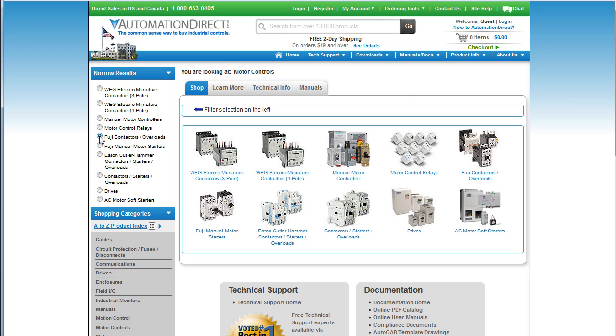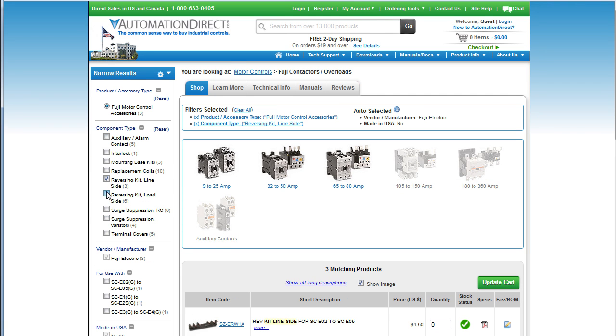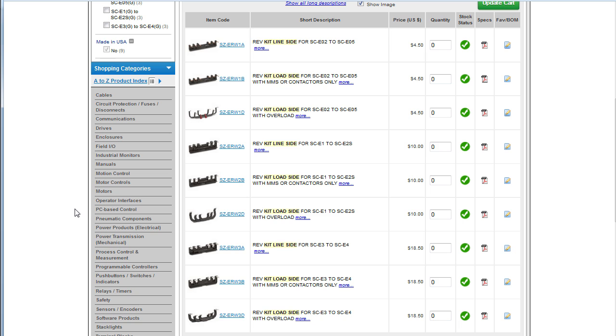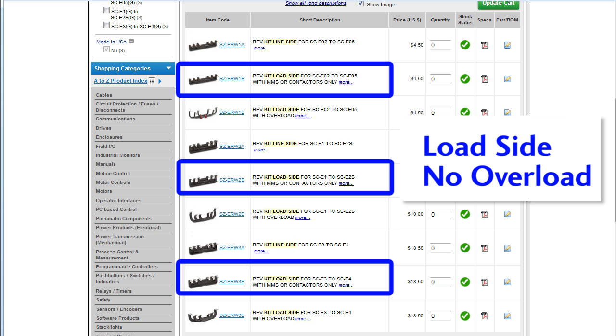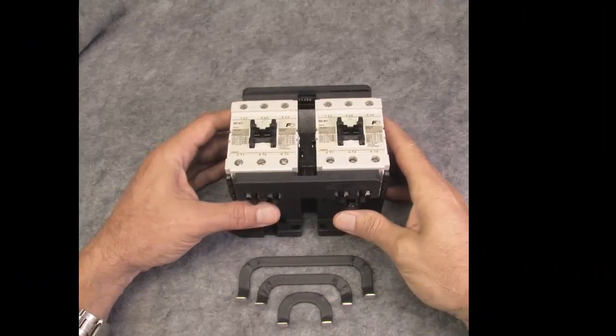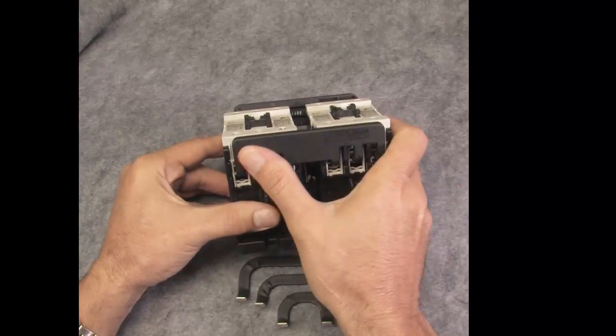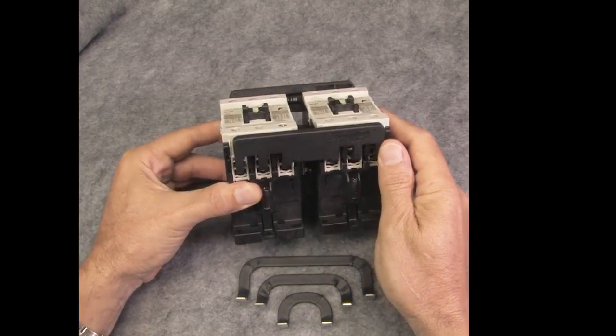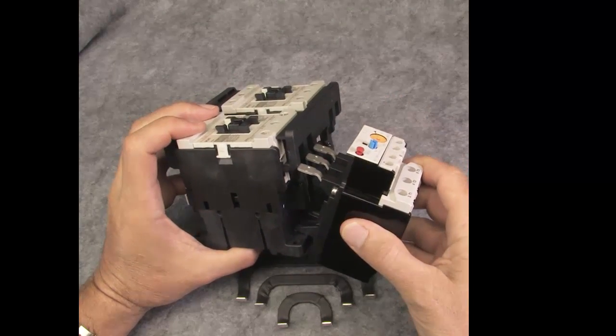For the Fuji family of contactors, select Motor Controls, Fuji and Fuji Accessories, Reversing Kits. There's one for the line side and one for the load side. There are three sizes for the line side, three sizes for the load side and another three sizes for the load side if you are using an overload. You'll see why in just a minute. This type is for setups where you are not using an overload. They are nice because they do the whole job with one molded part you just slide in. But they get in the way of adding an overload.